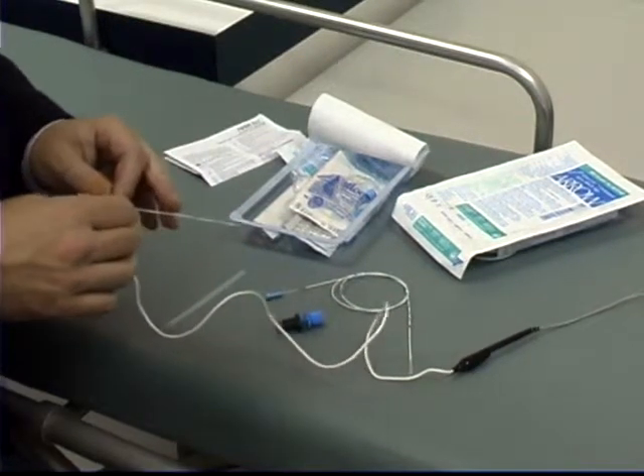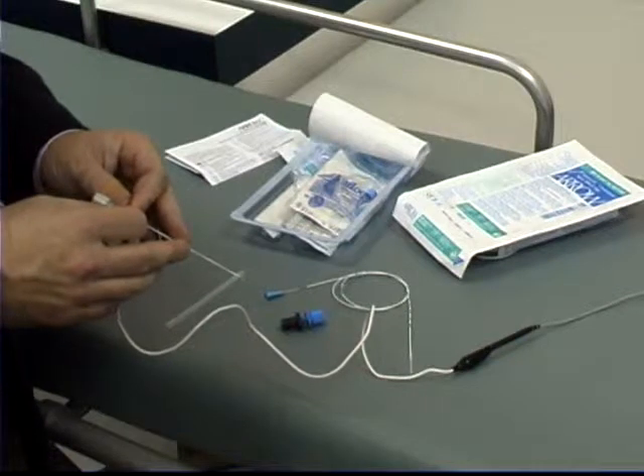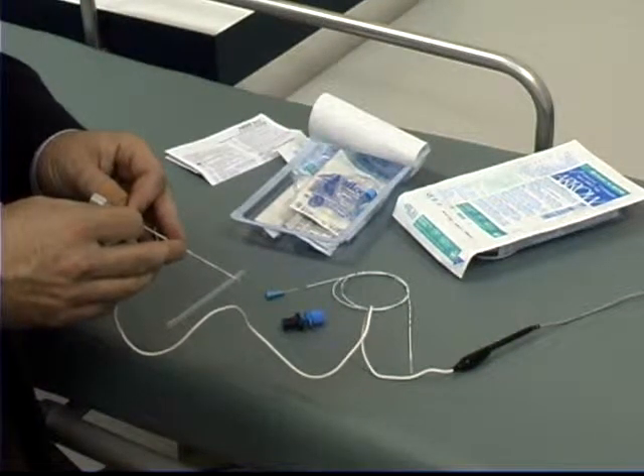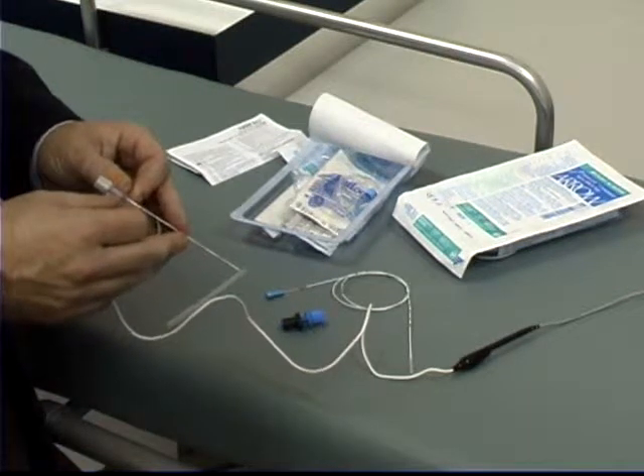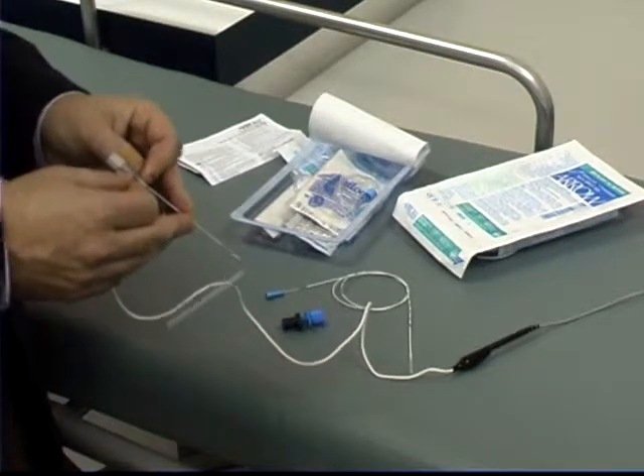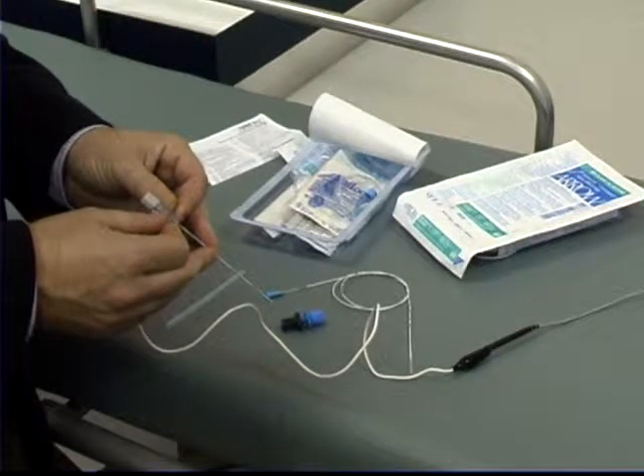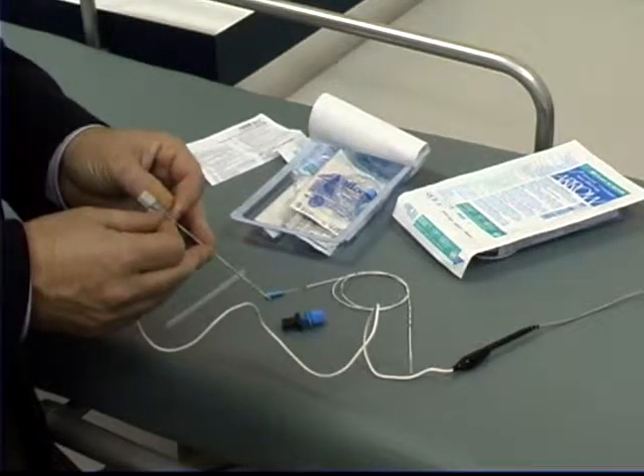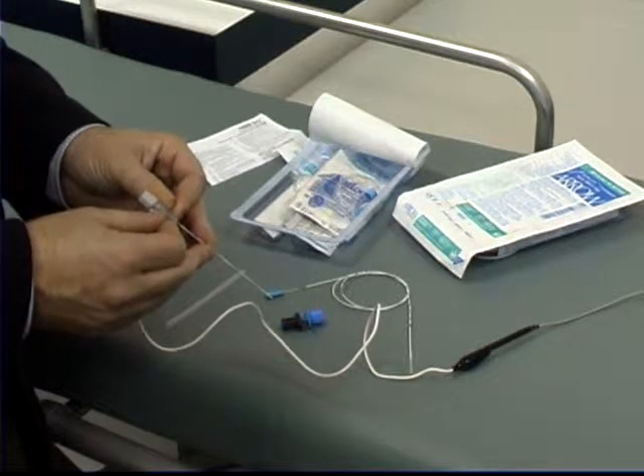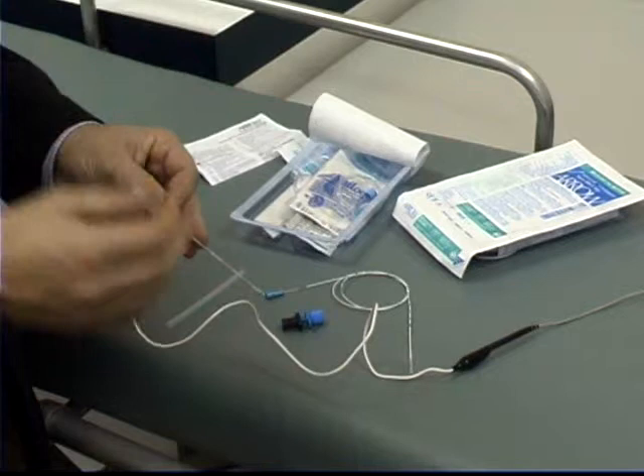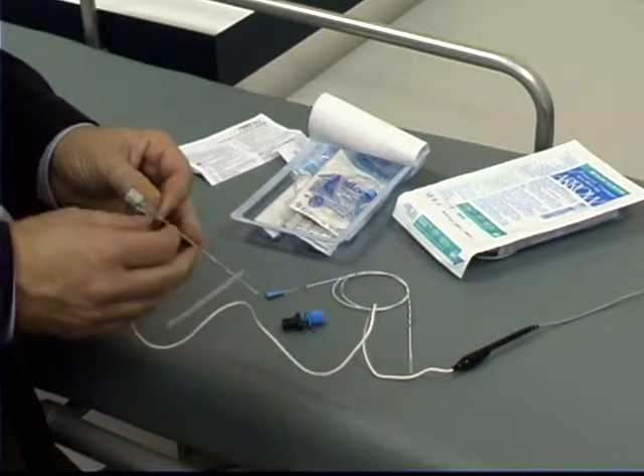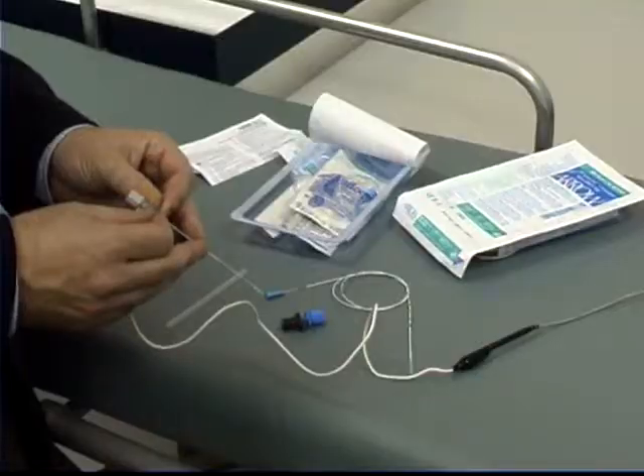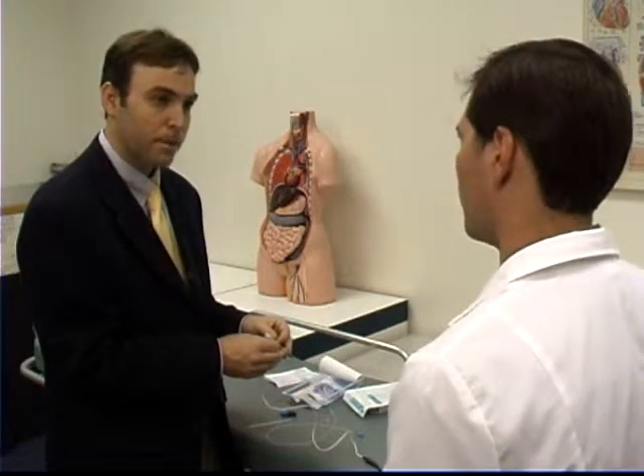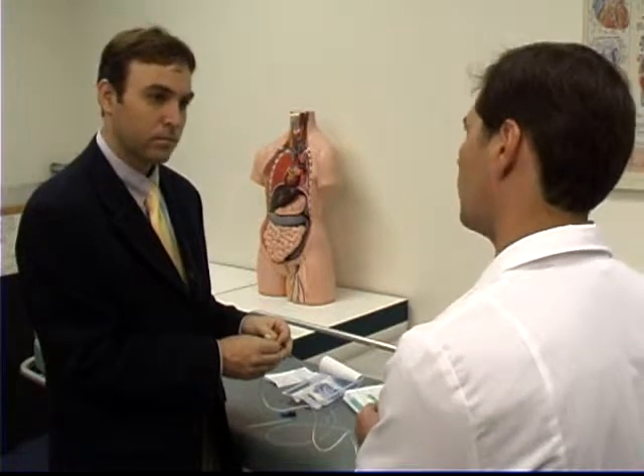Now at this point, what do you typically start your milliamp settings at? Is it somewhere between 1 and 1.5? We always start at 1.5 milliamps. Very similar to what I've heard. Do the same thing with our StimuCath needle. Start at 1.5, penetrate where you've made your landmarks, and as you begin to localize the nerve and get the twitch that you're looking for, you're going to dial down on the current. Most people have told me that they'll accept around 0.5 as an acceptable response. Once we get some response at 1.5, we'll go to 1, and we'll look to get the same vigorous response.